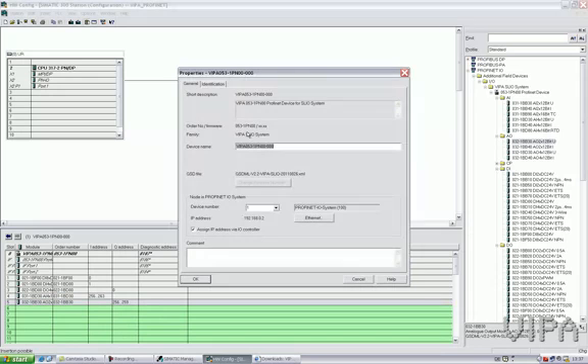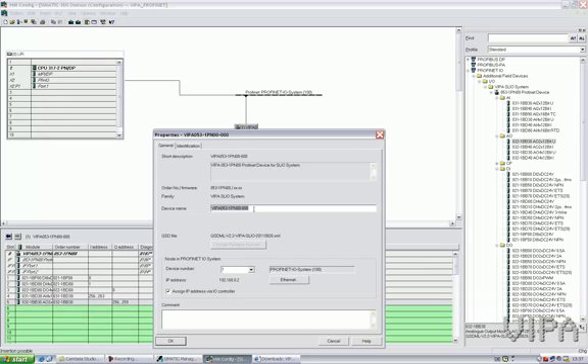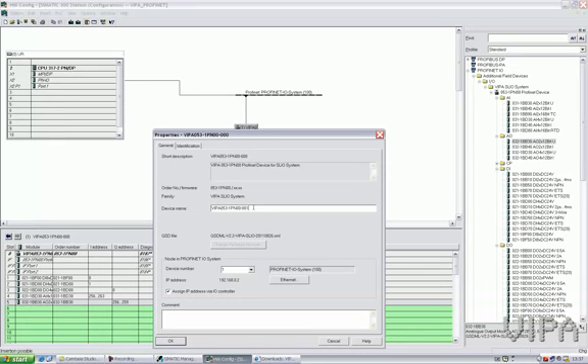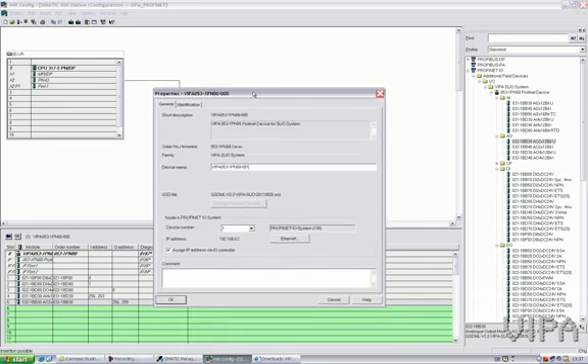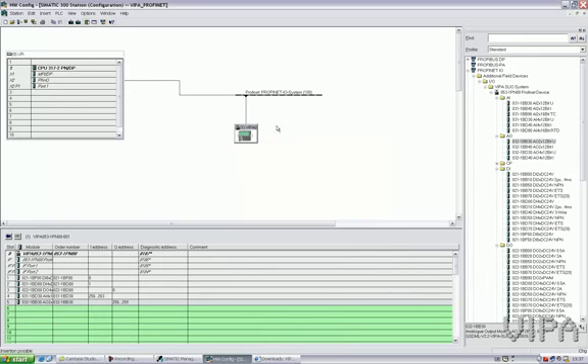I'll double-click this Profinet device. The most important thing on the Profinet device is the Profinet name. Now, here I can choose either to do the name setting through DIP switches - you can find this in the manual - or I can give it a name through Ethernet. In this case, I'll select the name setting with the DIP switches, which is quite easy when I need to exchange one. And press OK. As you may have noticed, I don't need to set any IP addresses, it's done automatically.